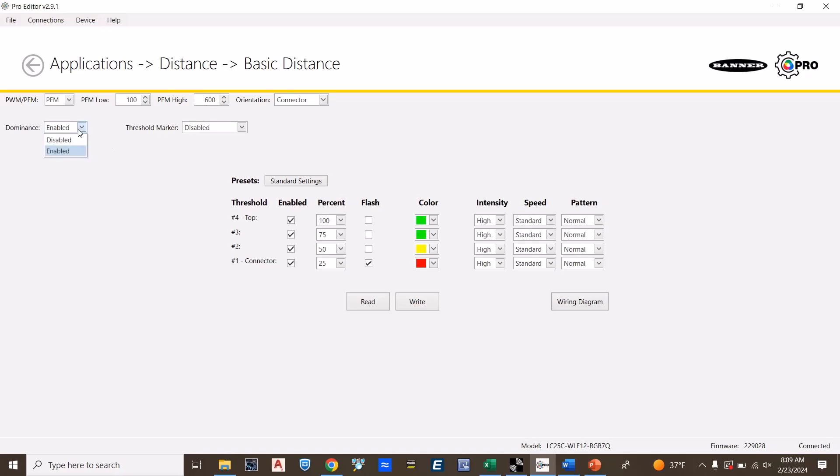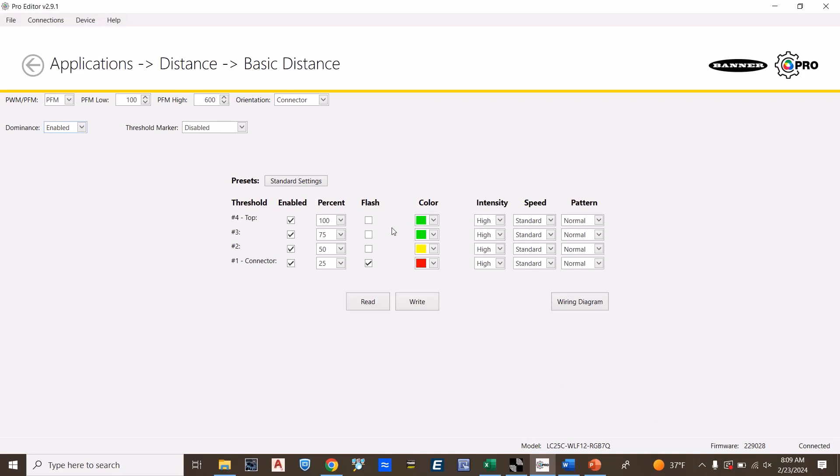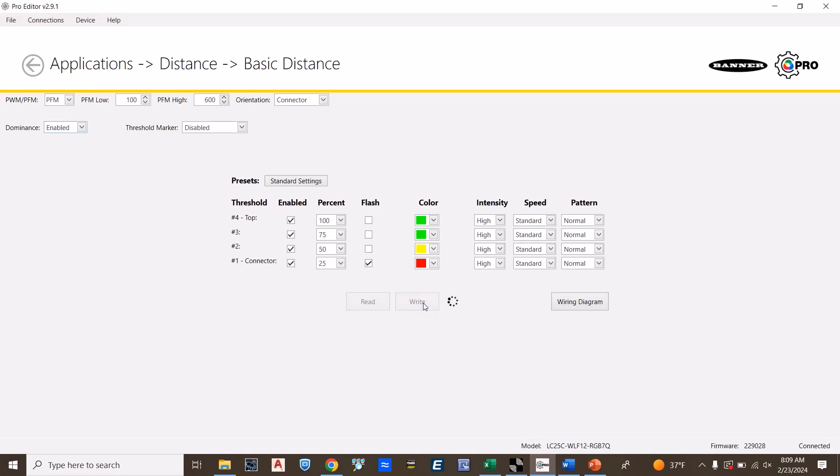I'm going to enable the dominance, and then select the colors accordingly. When the laser sensor has its highest output, it's going to indicate green. When it's at its lowest level, it's going to indicate yellow or red, and then flash at its lowest level. To write this configuration, select write.